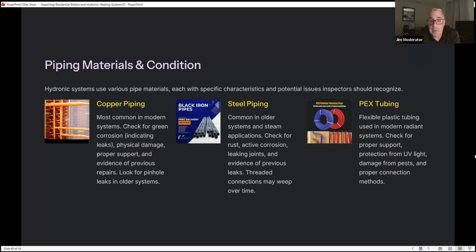Steel piping, common in older homes and steam applications: check for rust, active corrosion, leaking joints, and evidence of prior leaks. Threaded connections may weep over time. And PEX tubing, flexible plastic tubing used in modern radiant systems: check for proper support, protection from UV light, damage from pests, and proper connection methods.